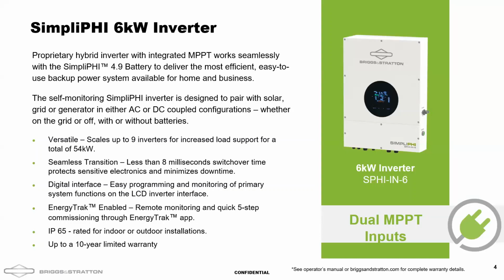There's a digital interface on the inverter, meaning you can program it from the face of the unit. However, you'll really want to use our EnergyTrak system. With the inverter, you'll purchase a gateway for each system, giving you access to program the inverter remotely through the Bluetooth of your cell phone or tablet. This makes for much easier commissioning, and you'll also be set up to monitor the system through that same app, which we'll talk about in more detail.